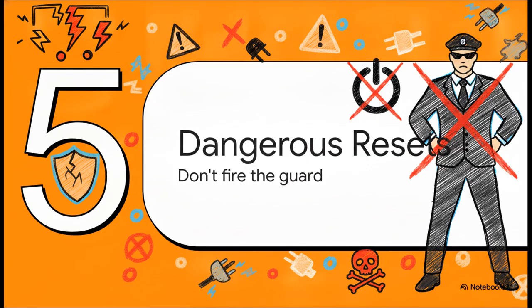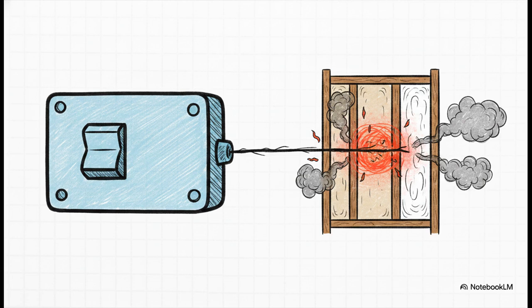Section 5, dangerous resets. Don't fire the bodyguard. Human error is often the absolute biggest danger here. I mean, we just want the power back on, but replacing a breaker with a higher rating allows existing wires to overheat. Upsizing a breaker without upgrading the wiring is essentially firing the bodyguard while the threat is still inside your house. The wire size, the insulation, connection quality, and ambient temperature all dictate what is safe. If you just slap a bigger breaker on smaller wires, you're literally allowing them to slowly cook inside your walls.